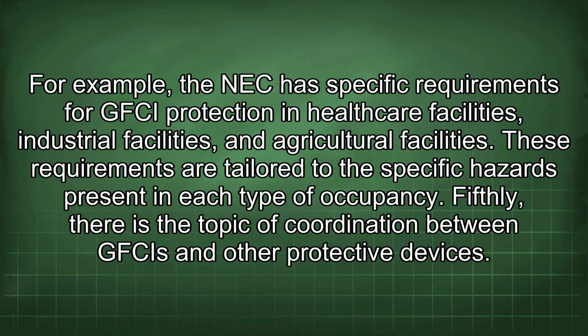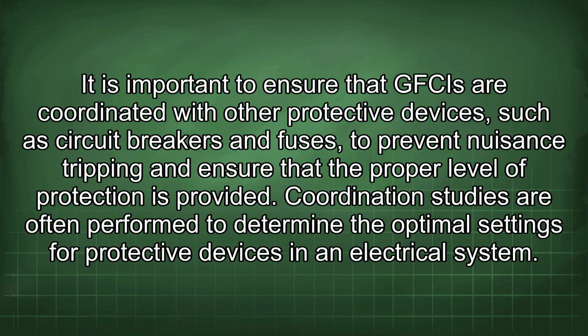Fifthly, there is the topic of coordination between GFCIs and other protective devices. It is important to ensure that GFCIs are coordinated with other protective devices such as circuit breakers and fuses to prevent nuisance tripping and ensure that the proper level of protection is provided. Coordination studies are often performed to determine the optimal settings for protective devices in an electrical system.